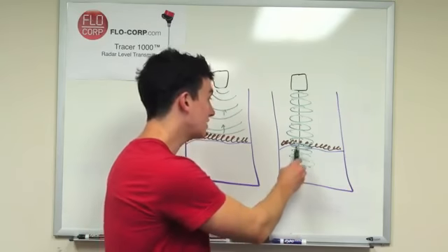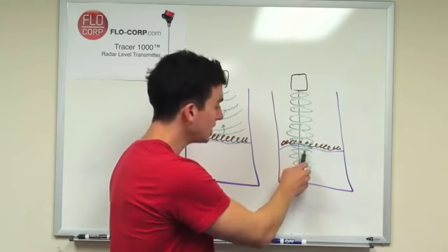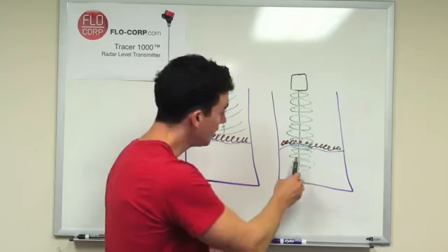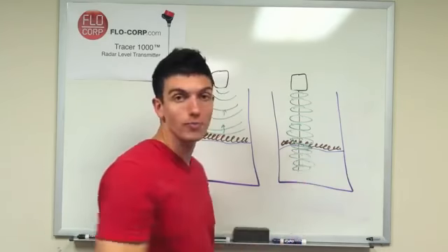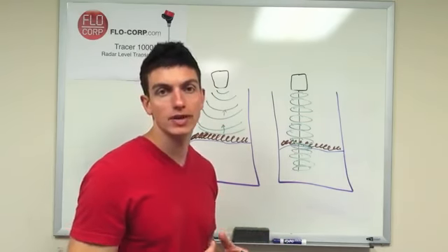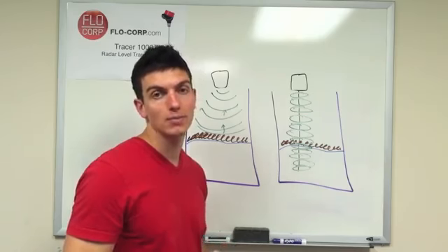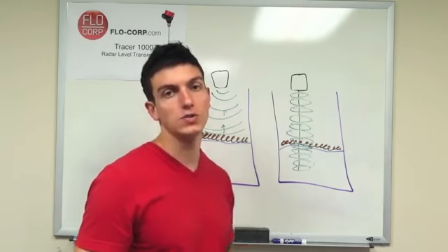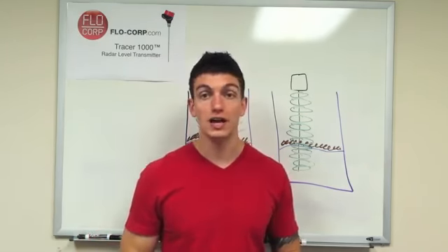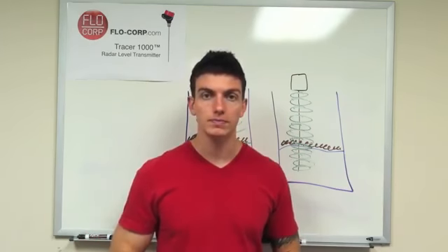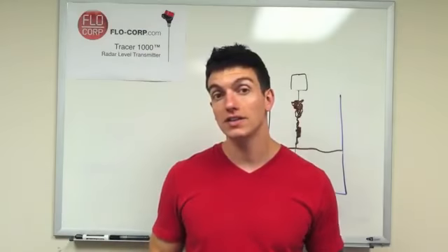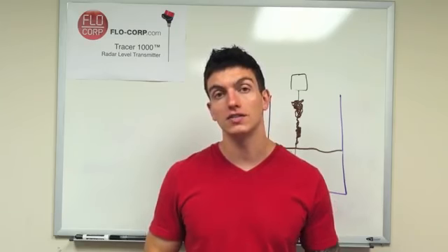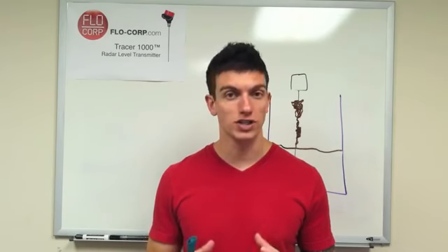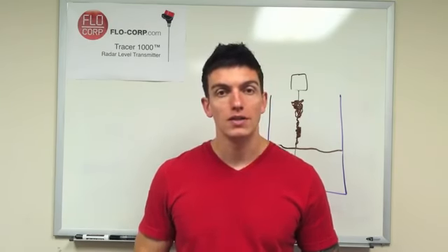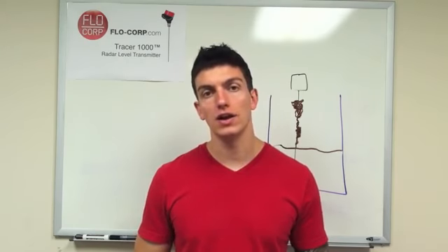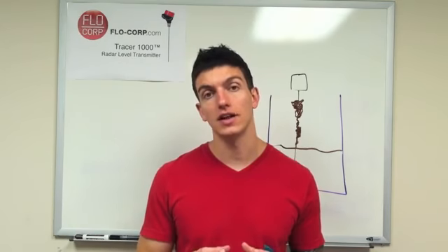Essentially, it's going to take this strongest signal here when it first gets into the liquid. It's going to ignore the foam, and we're going to get an accurate measurement. So guided wave radar becomes very ideal in a situation with foam where ultrasonic really cannot cut it. The final process condition I want to talk about is a situation where there would be an emulsion on the probe. This only really applies to guided wave radar as it is a contacting level device.